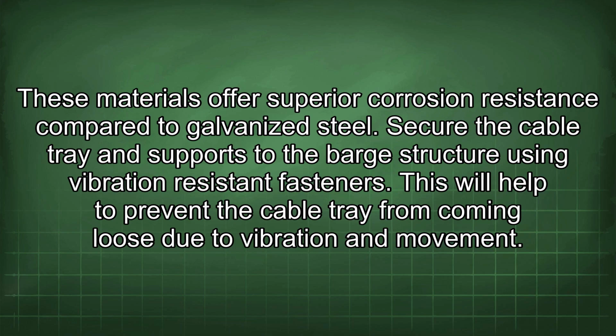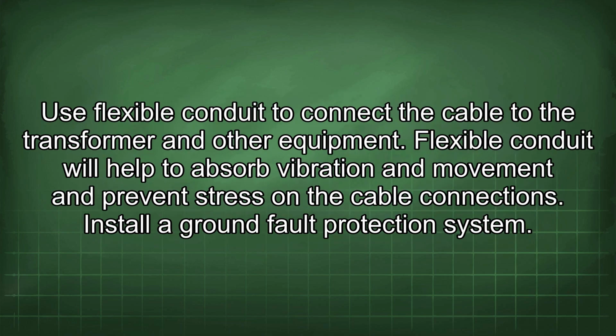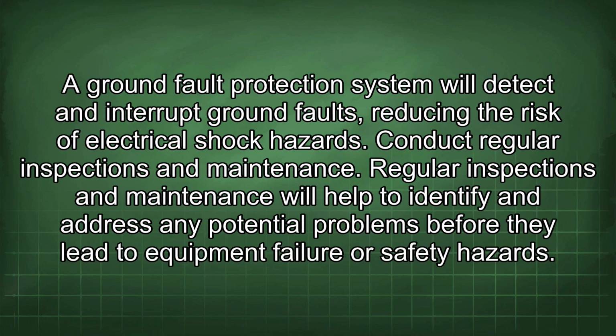Secure the cable tray and supports to the barge structure using vibration-resistant fasteners. This will help to prevent the cable tray from coming loose due to vibration and movement. Use flexible conduit to connect the cable to the transformer and other equipment. Flexible conduit will help to absorb vibration and movement and prevent stress on the cable connections. Install a ground fault protection system. A ground fault protection system will detect and interrupt ground faults, reducing the risk of electrical shock hazards.